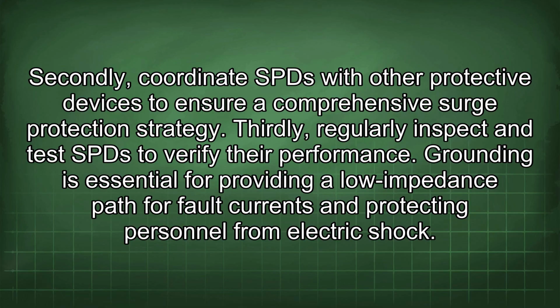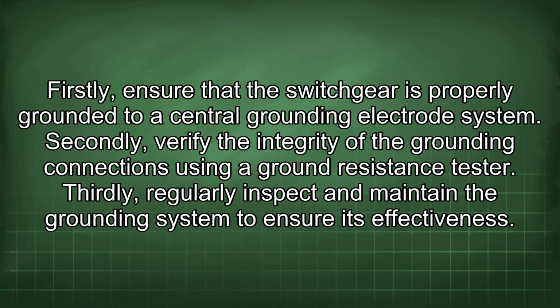Grounding is essential for providing a low impedance path for fault currents and protecting personnel from electric shock. Firstly, ensure that the switchgear is properly grounded to a central grounding electrode system. Secondly, verify the integrity of the grounding connections using a ground resistance tester. Thirdly, regularly inspect and maintain the grounding system to ensure its effectiveness.